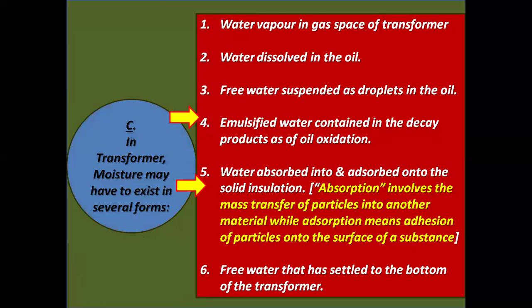See, in a transformer, moisture may exist in several forms. One, water vapor in the gas space of the transformer. Two, water dissolved in the oil. Three, free water suspended as droplets in the oil. Four, emulsified water contained in the decay products of oil oxidation. Five, water absorbed into or adsorbed onto the solid insulation.